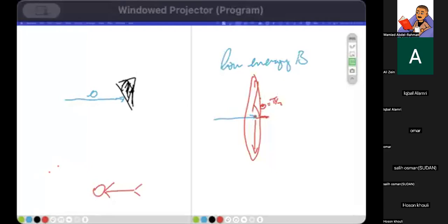Let's look at the physics. The physics tells us that the maximum intensity is at 90 degrees. So it would make sense. The production of X-rays is already really inefficient, so it would make sense that we put a target such that when X-rays are produced, we put the patient in the direction where we get maximum intensity.